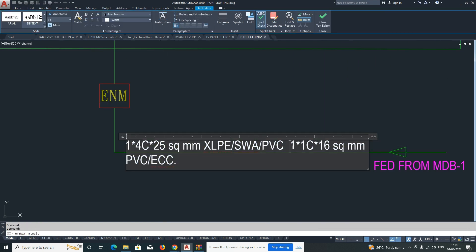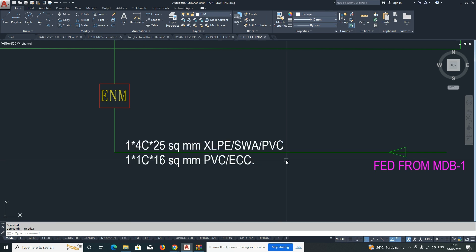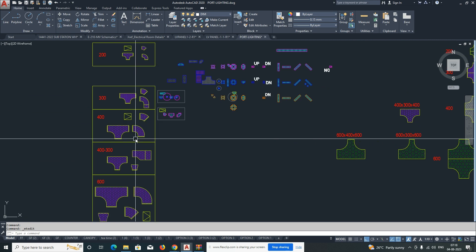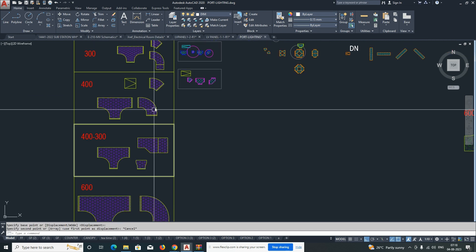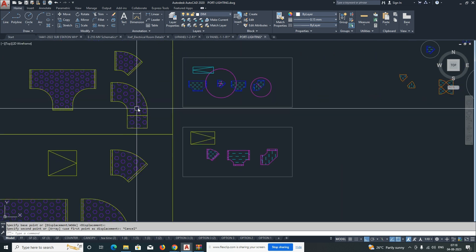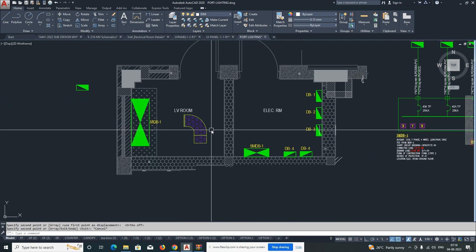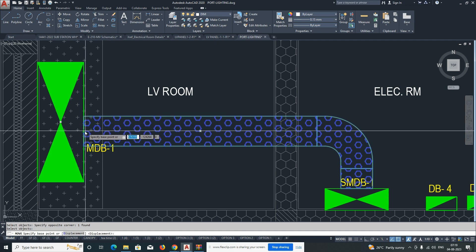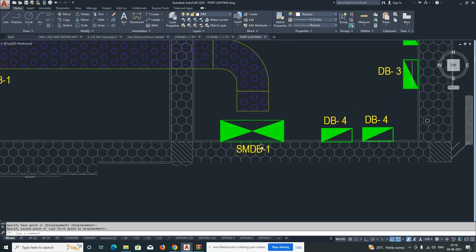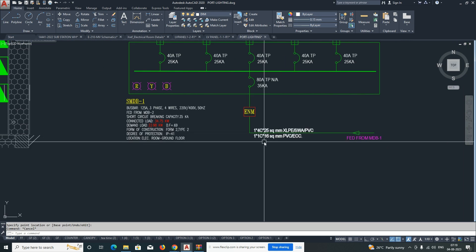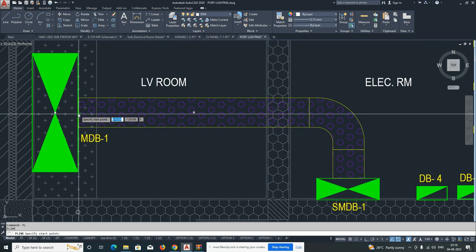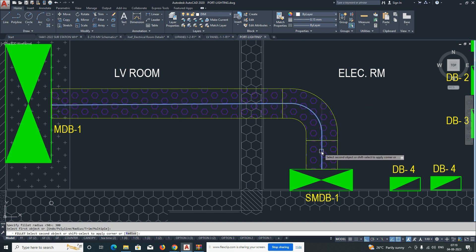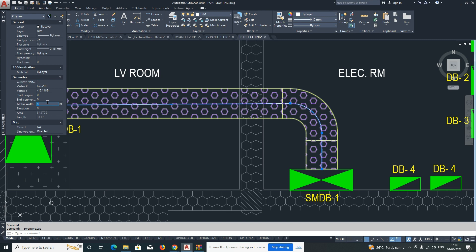The 25mm XLPE SWA PVC cable is coming from MDB1 and connecting to SMDB-1. We need to draw some cable trays. There will be some calculation for cable tray sizing, and as per that we design the cable trays. I'm choosing a 300mm cable tray, copying it, and placing it here. I'll stretch it and connect it to the panel. I'll draw one cable like this — 300mm fill, and global width of 25 for the cable to the LV panel.